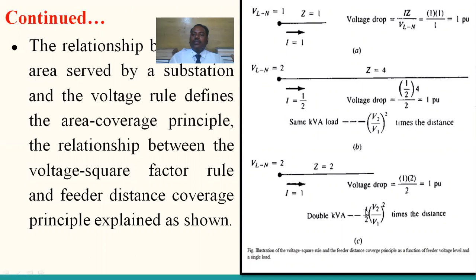Yes. For constant percentage voltage drop and uniformly distributed load, the feeder service area is proportional to line to neutral voltage new by line to neutral voltage old whole square into whole power 2 by 3. That is, for constant percentage voltage drop and a uniformly distributed load, the feeder service area is proportional to the voltage square factor whole power 2 by 3.